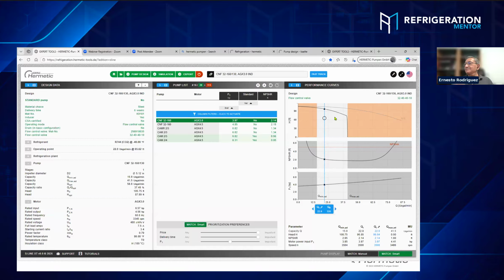for many evaporators, many coils, or a single coil. I want to explain in the next slide of the presentation exactly how the thing works. Because that distance there means in our design condition, we're at about 62 feet of head approximately, but we can go up to almost 100, or 90, like 95. Yes, that much range to play with when we're loading and unloading different cases, and at defrost and not defrost, things like that. Okay, beautiful. Yeah, the regulator control and all this see how the system is demanding liquid.